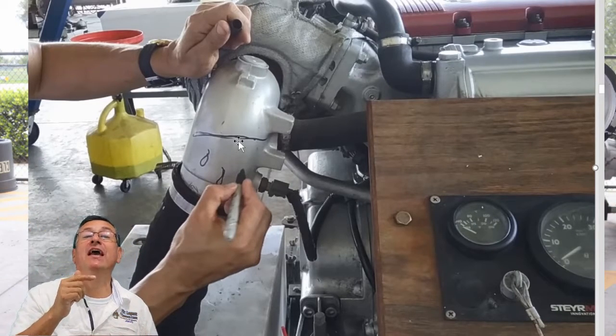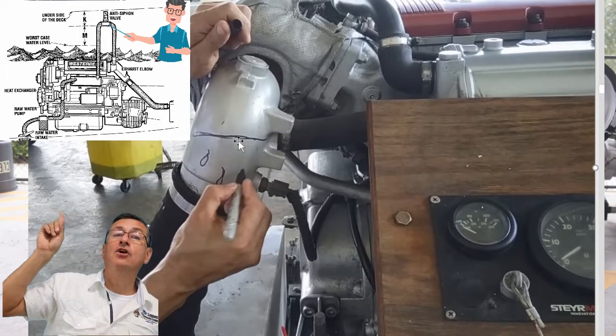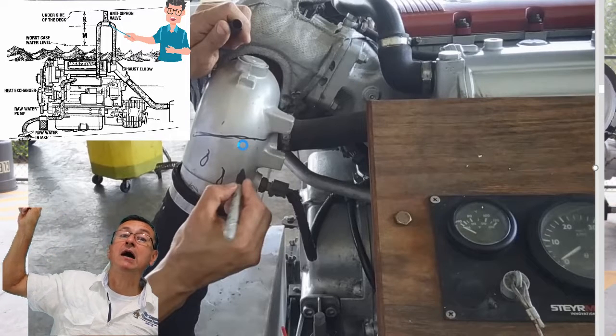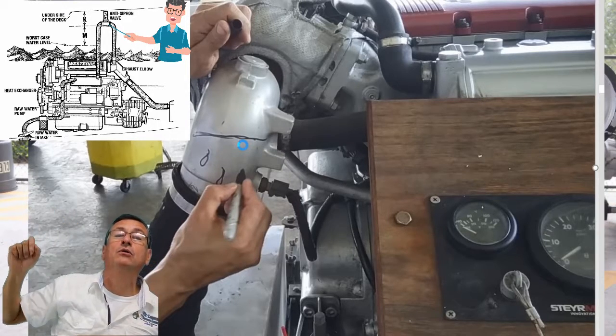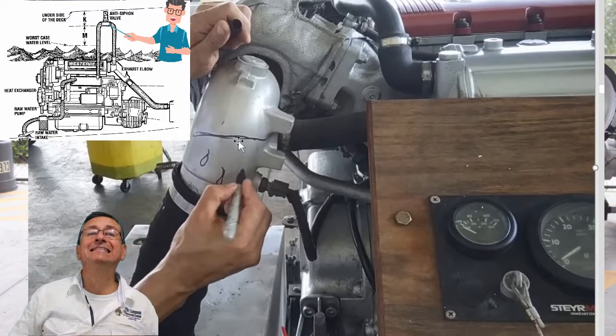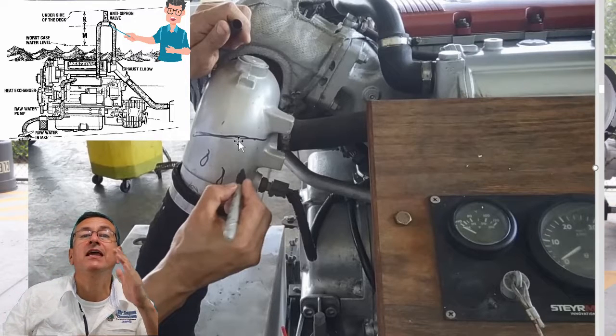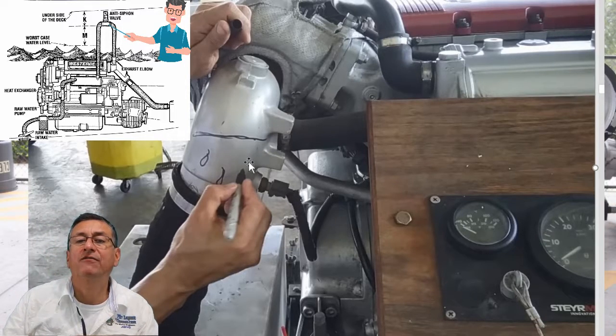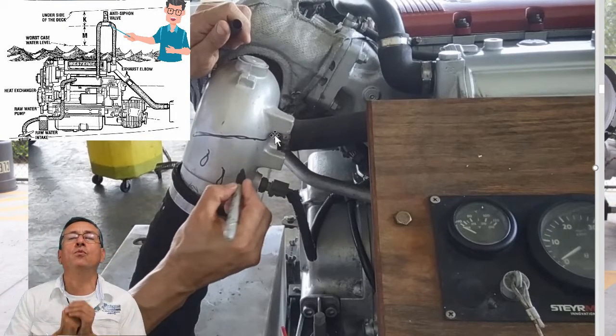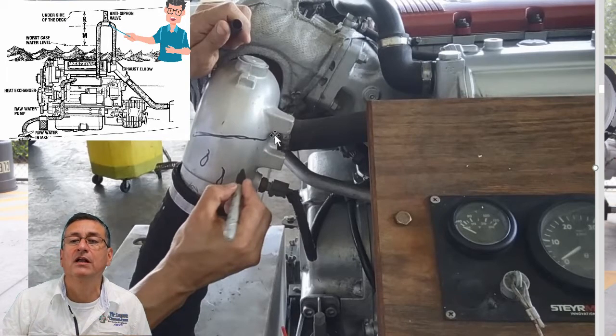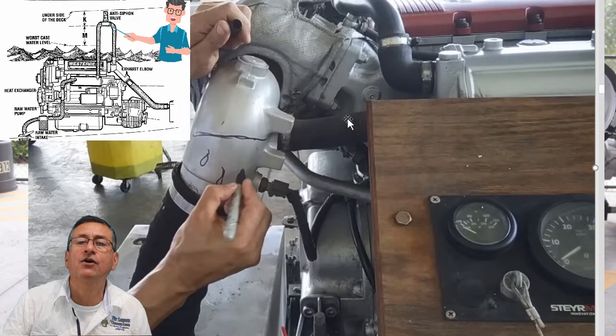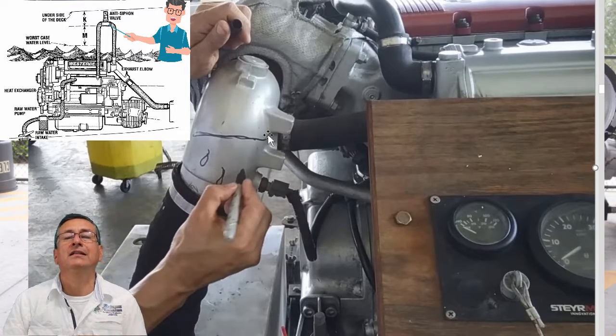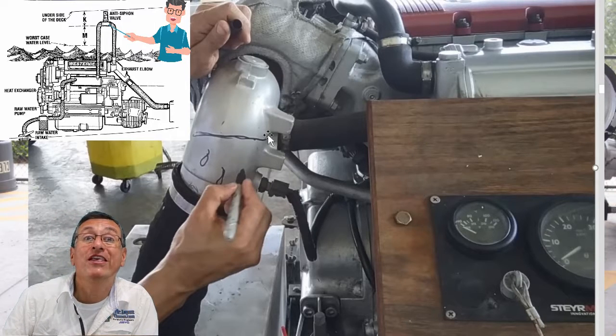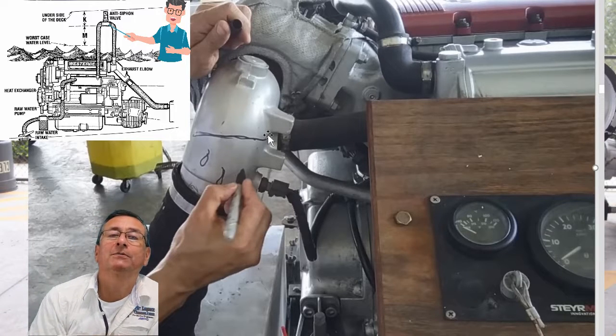If the engine is located below the water line, this hose should go up over the water line, 12 inches, and return down. We are going to install an anti-siphon there. This is very important, my friends. I am going to interrupt this hose, send it up 12 inches over the water line, and return here. That's the point where I am going to install the anti-siphon. That's required to avoid suctioning salt water during cranking.